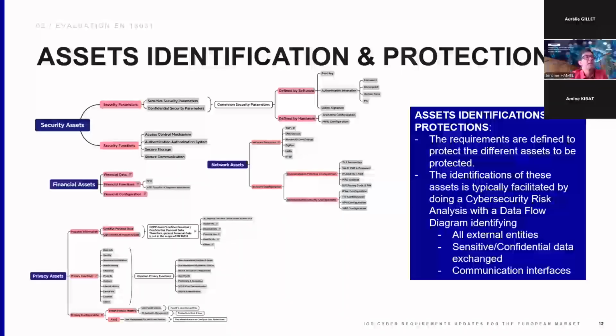So this step to identify assets is very important because this is, let's say, the starting point of all the evaluation. The way that we suggest manufacturers do it is really to perform a cybersecurity risk analysis, and especially what we call the data flow diagram, which is identifying all the external entities to the product. So what are the different entities which can exchange data with the product? And then what are the sensitive and confidential data which are exchanged or stored on the product? And what type of communication interfaces are used?